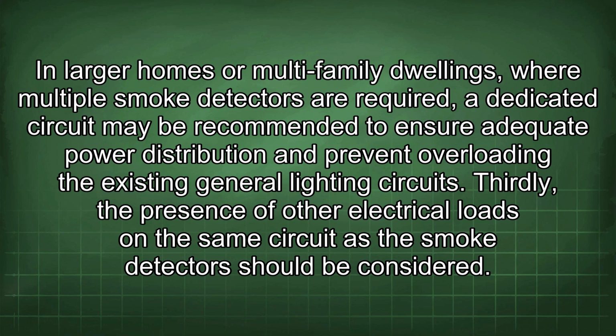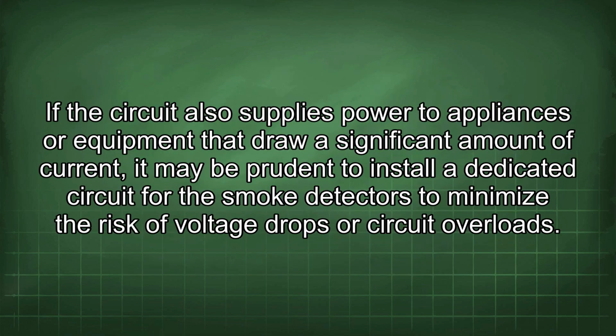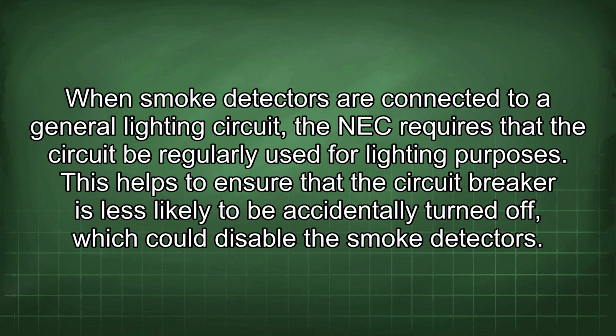Thirdly, the presence of other electrical loads on the same circuit as the smoke detector should be considered. If the circuit also supplies power to appliances or equipment that draw a significant amount of current, it may be prudent to install a dedicated circuit for the smoke detectors to minimize the risk of voltage drops or circuit overloads. When smoke detectors are connected to a general lighting circuit, the NEC requires that the circuit be regularly used for lighting purposes.